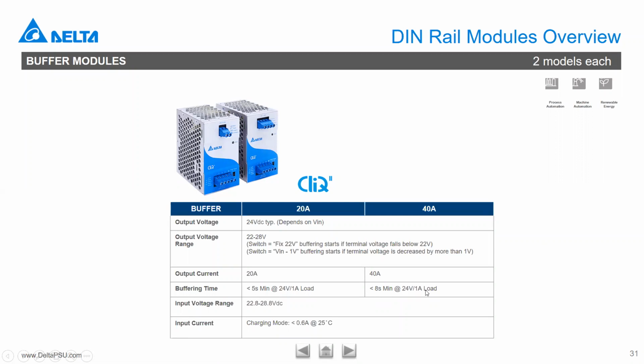So if your system requires a maximum of 40 amps, then at 40 amps we are looking at a hold up time of approximately 250 milliseconds. So once again, the buffering time is from milliseconds to a maximum of 8 seconds.